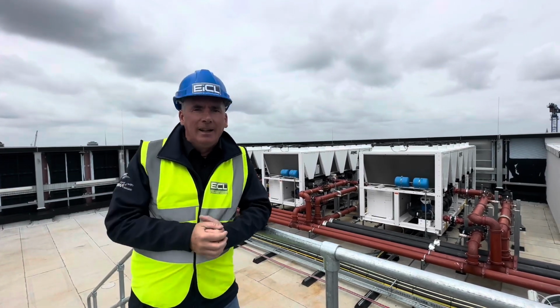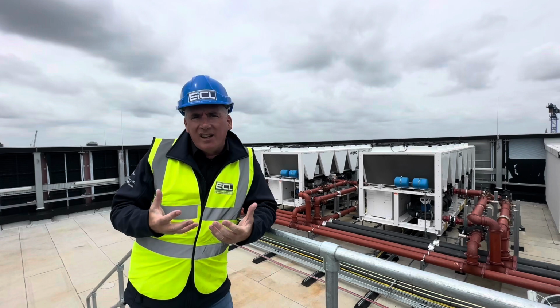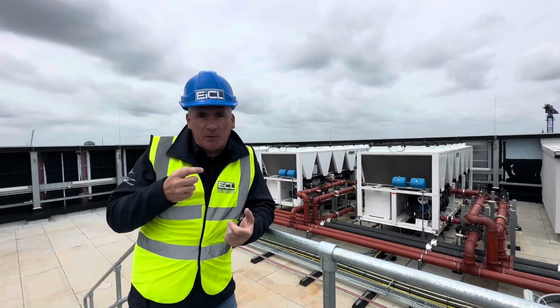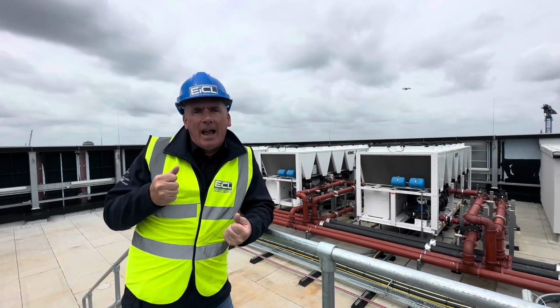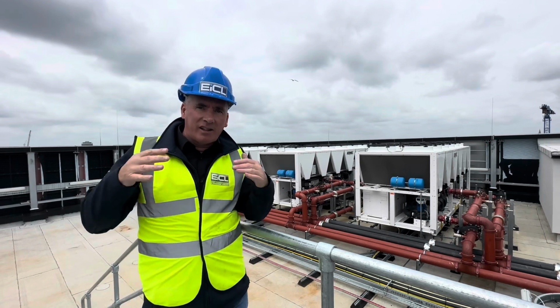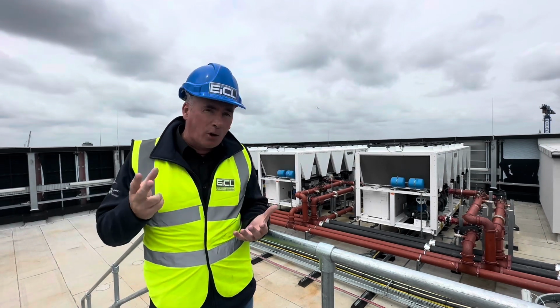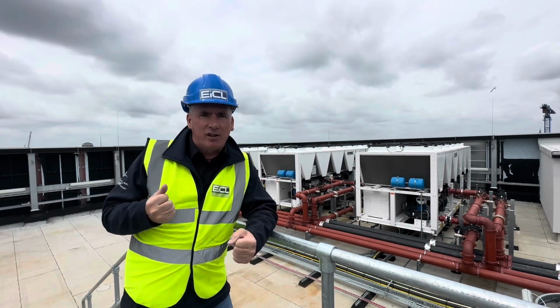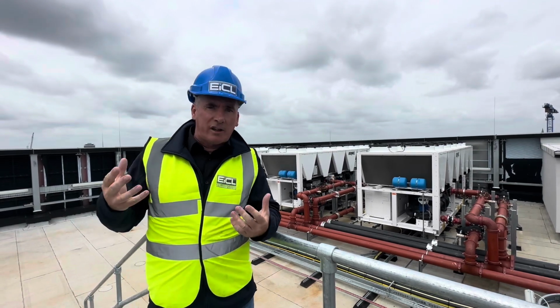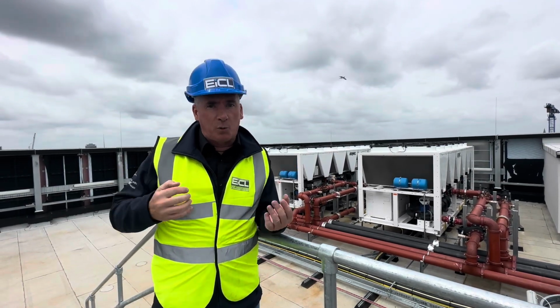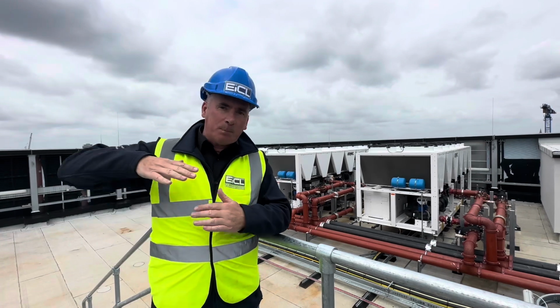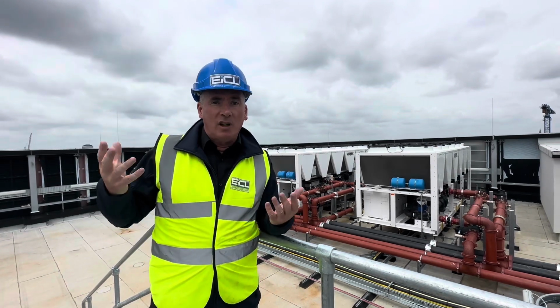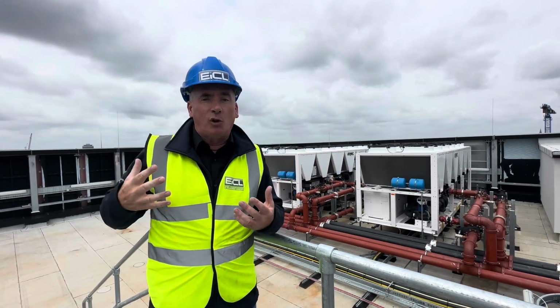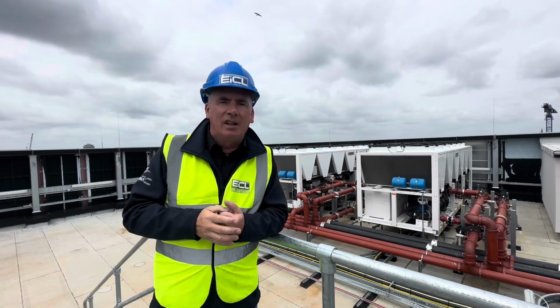because you're getting your heating for free. So we normally design these systems, a lot of people will be familiar with this from the designer training program that we give, where we explain that you want to design your heating system as low as possible, typically 45-40, and you'll find it's very much the industry norm nowadays. And then we use the WWB, the water booster, which I'll show you in a minute in the basement, where we can boost the temperature up to as high as 80 if need be, but you don't necessarily need to go that temperature.